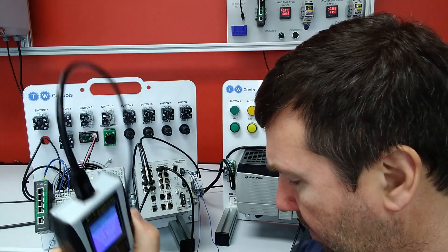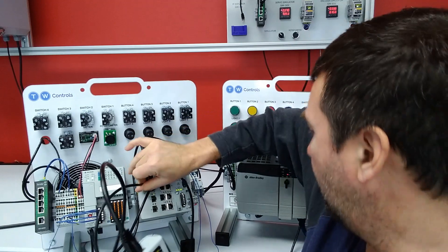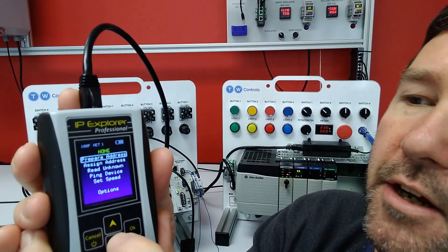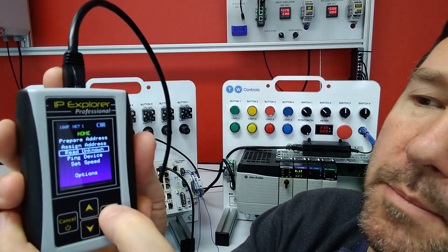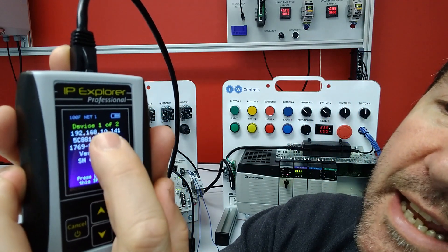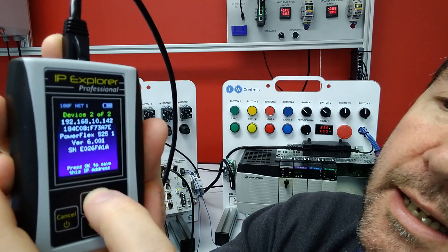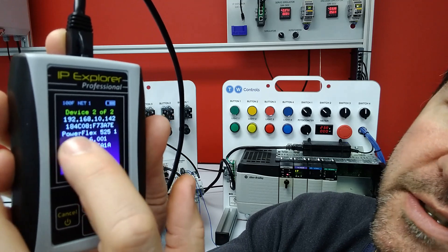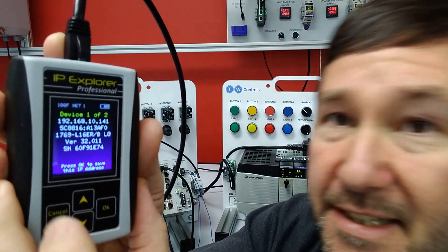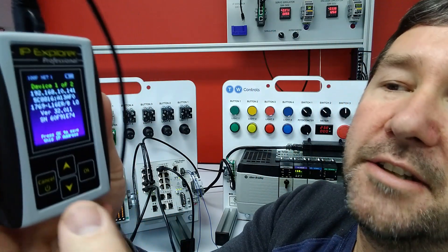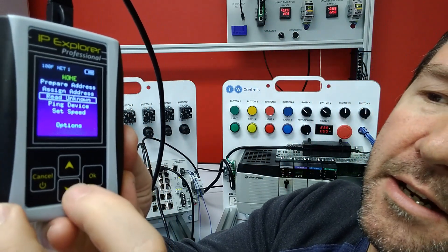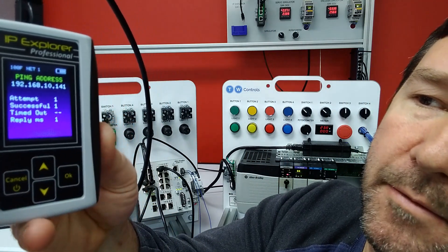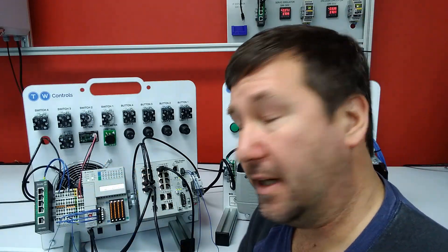So I'm going to plug our SIM IPE into network 10. And now I'm going to go first, well, first, let's go and read unknown IP. So that way we can see what is out there. And we're going to say we have two devices. The first one is 192.168.10.141. And the second one is 192.168.10.42. And all right, 42, it says right there is a PowerFlex drive. 41 is our 1769 Compact Logix PLC. So now what I'm going to do is I'm going to hit the OK button. And what that's going to do is it's going to save it as our target IP address. And now I can go here and I can ping the device. And we're attempting to ping. We're getting a successful ping. So we're good as far as our connection to it.